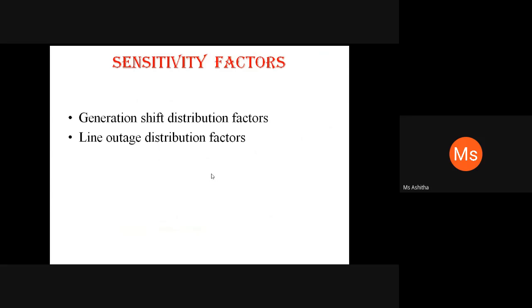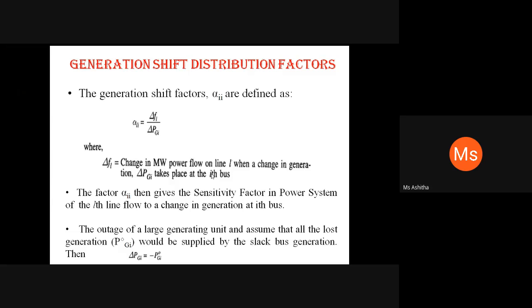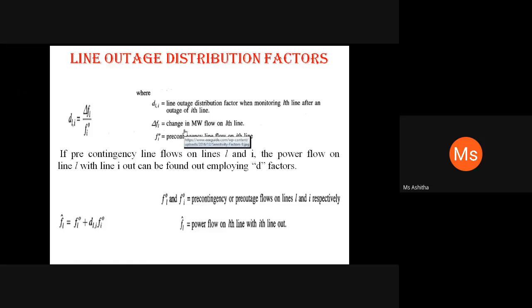Then sensitivity factors. Mainly there are two different sensitivity factors. One is the generation shift distribution factor and the other is the line outage distribution factor. The generation shift distribution factor can be defined as the change in the megawatt power flow on the line to the change in the generated power that takes place at the ith bus. Similarly, the line outage distribution factor can be defined as the change in the megawatt power flow to the pre-contingency line flow on the ith line.